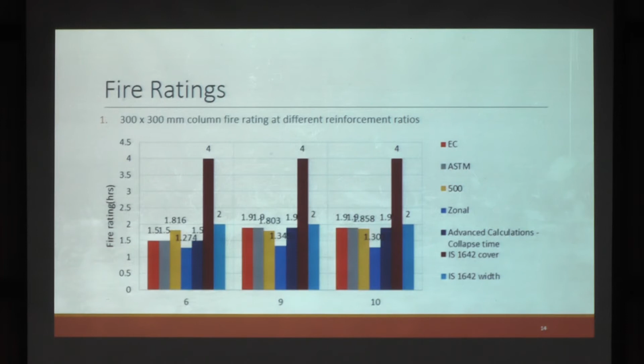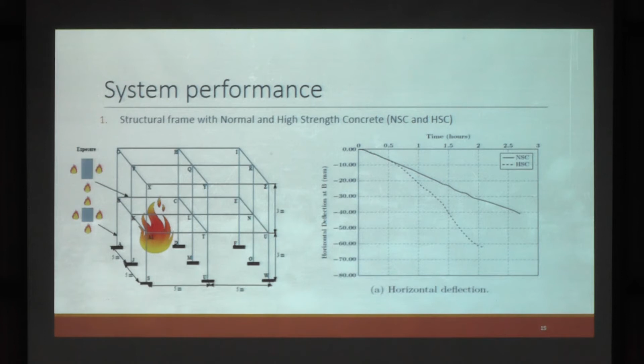And using this code, we have tried to do several performance-based evaluations. This is another counterintuitive result in general. Nowadays, since we are building tall, a lot of emphasis is on high-strength concrete, which is concrete more than 50, 60 megapascals in strength. The conventional wisdom is that since it is higher strength, it will behave better in fire. But that doesn't happen in general. This dotted graph is the deformation of a high-strength concrete column, whereas this one is for a normal strength concrete column. So it actually undergoes greater deformation, which means it might fail earlier.